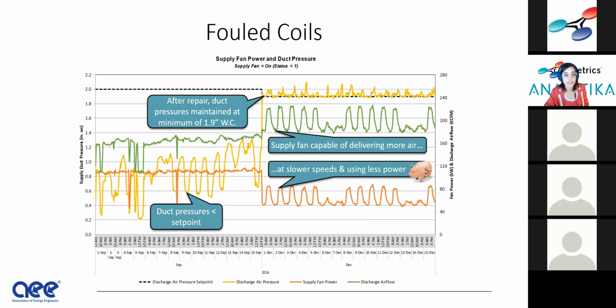And that's what the fault engine is reading. Okay, we're not meeting set point. In this case, why? That was the question, and we could deduce that it was fouled coils. So after the coil replacement, all the duct pressures were maintained at their set point, and we were delivering more air at slower speeds using less fan power.